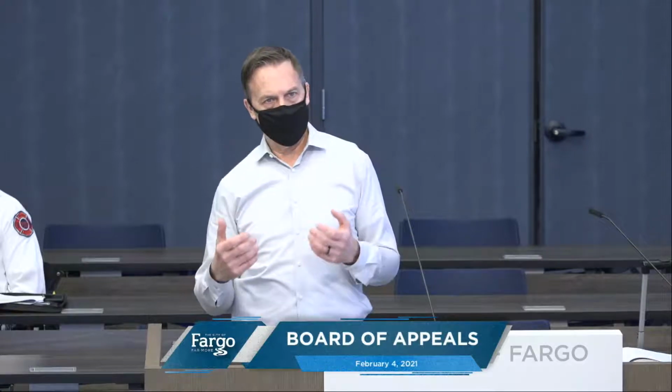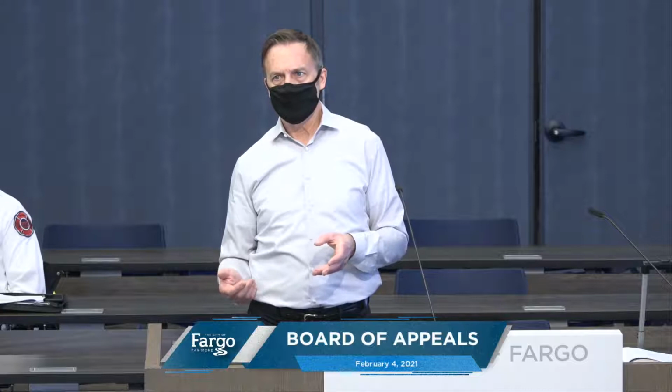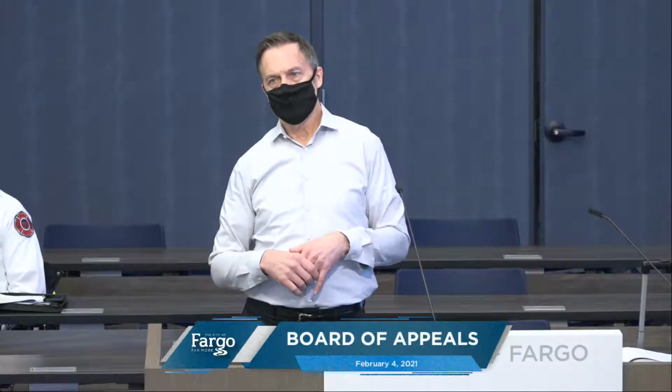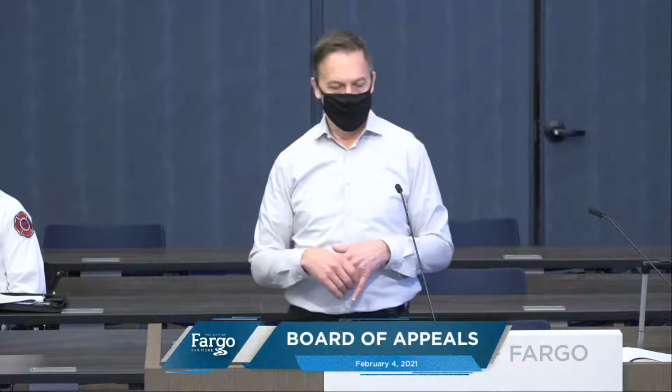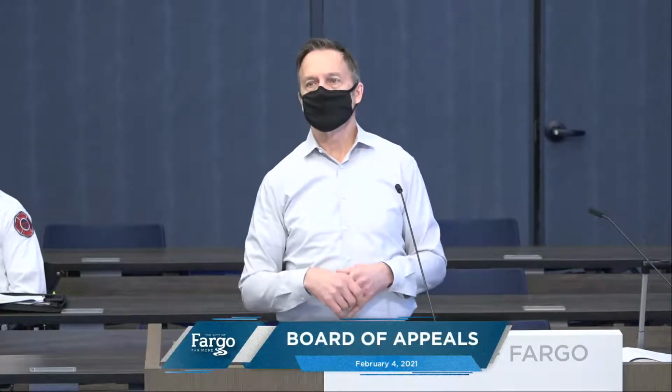You turn an open parking garage where private people are coming in and parking every day, they're coming and going. Are they expecting to have a stall next to them with a gas can in it? You're not putting gas cans in that open parking garage normally. It says, hey, this is new, it's different. You're going to see an excerpt from, I consider one of the best code guys in the country, Doug Thornburg, who, in our opinion, clearly states it.